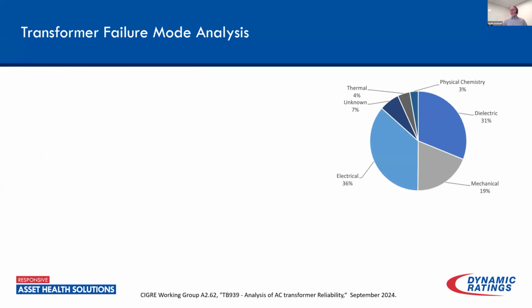So to begin with, the first thing I wanted to look at was, is there any truth? Are we seeing higher failure rates in renewable applications versus our traditional applications? Unfortunately, this data here is from the CIGRE Technical Bulletin 939, which was completed in 2024, so it's relatively recent. And unfortunately, even CIGRE recognizes that they really don't have good data that focuses just on renewable applications when it comes to those generator step-ups. So the data that we're looking at here is basically all transformers. This could be just a standard distribution transformer, a transmission-based transformer, or it could be a generator step-up.